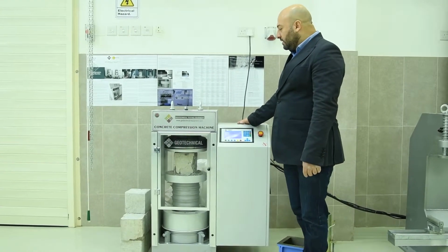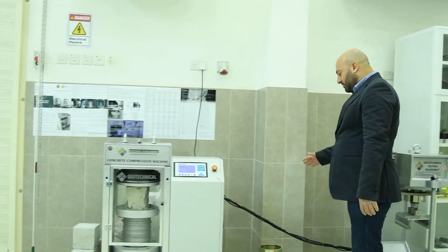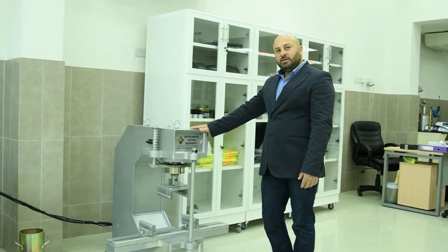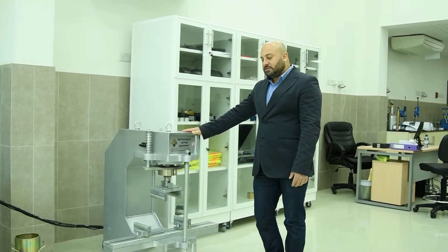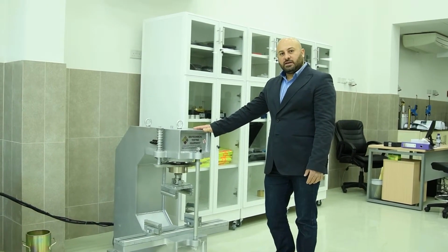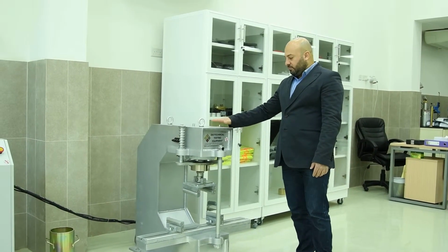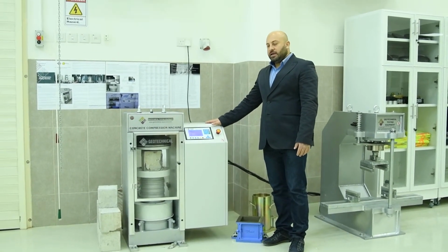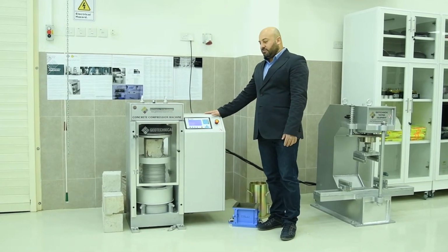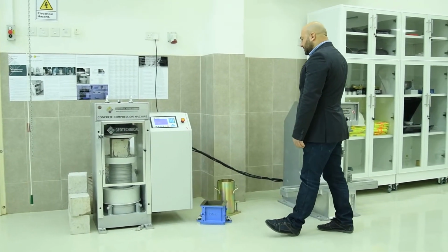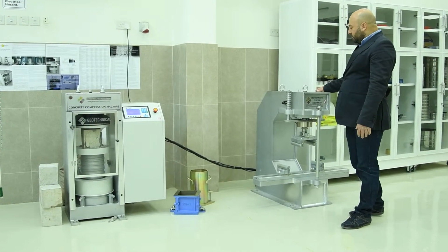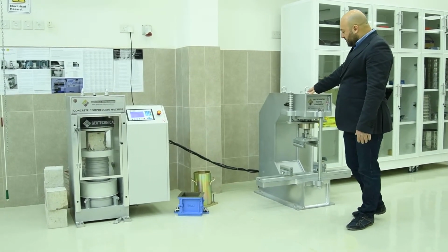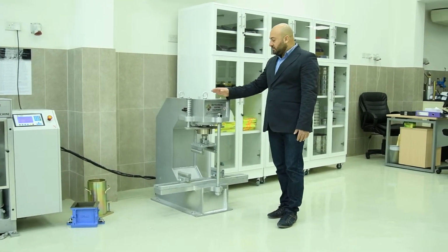At the same time, we'd like to mention that this machine, as I said previously, can be connected to a flexural machine, which is also used to test beams, flagstones, and curbs. Both machines are controlled from this power pack, and both of them will give you the results. Different capacities, as I said, are available for the compression machine as well as for the flexural machine. We have 100, 200, and 300 kilonewton flexural machines available. This is a C-type frame of a flexural machine.